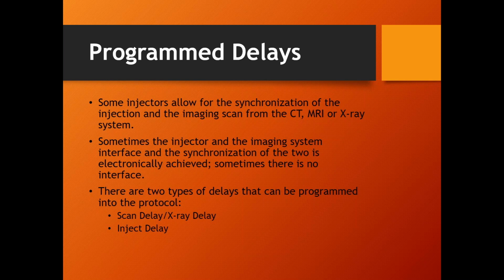Inject delay. Now the opposite of that is we're going to start this procedure, but the injector is going to start injecting first, and so many seconds later, the imaging system is going to start imaging. For CT and MRI systems, which are a CT scanner and an MRI scanner, it's called scan delay. But for angiographic procedures, that's an X-ray system, not an X-ray scanner, it is referred to as an X-ray delay. So 3 terms, but 2 meanings.